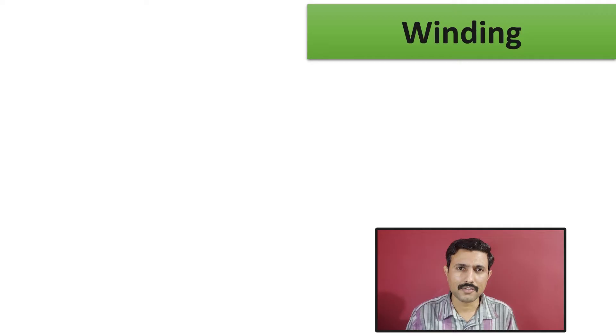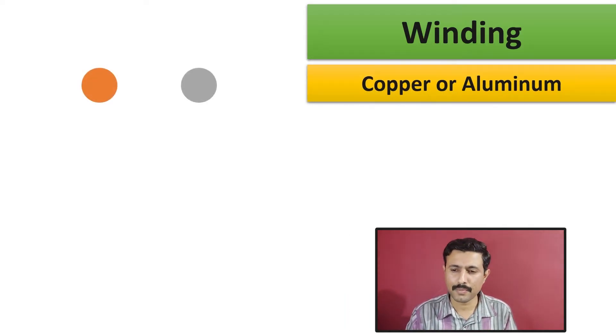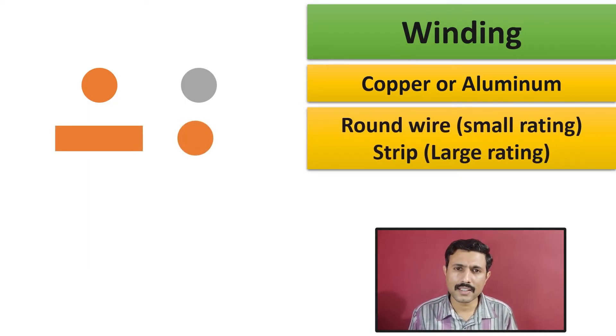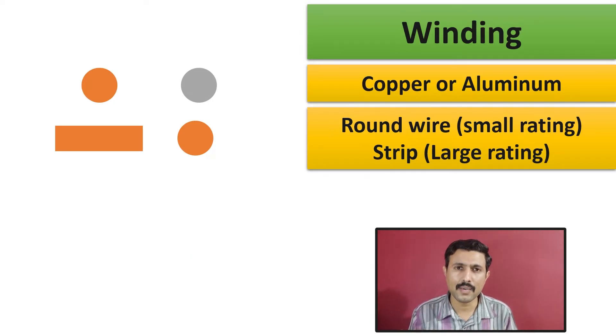The first component of transformer is winding, and this is the heart of transformer. This winding is either made up of copper material or aluminium material. Most of the time it is made up of copper material, but when cost is an important factor, aluminium can be chosen. In winding, either a round wire conductor is used or a strip conductor is used. When the rating of transformer is small, round wire conductors are used, and when the rating is larger and more current is going to flow, a copper strip is preferred.